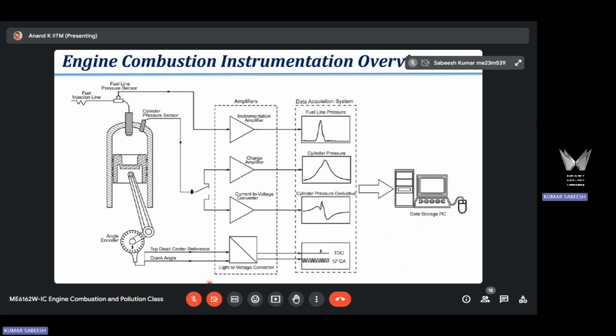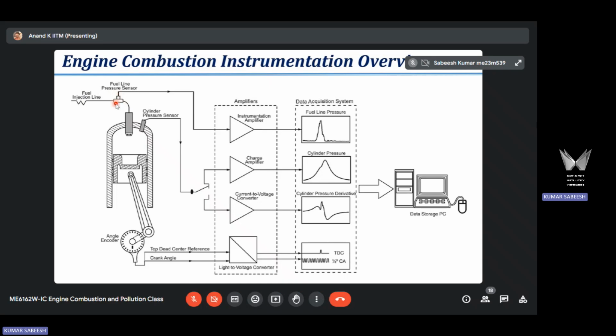So before that, I'm giving you an overview of combustion instrumentation here in this picture. So what we have here is the injector. This is a fuel injector. This is a high pressure fuel line. Here you have one sensor. This sensor that we have is a piezoresistive type sensor. This is called the fuel line pressure sensor. This sensor is required only if you have a mechanical fuel injection system.